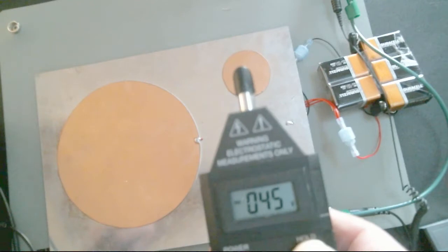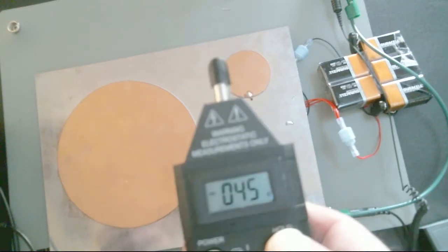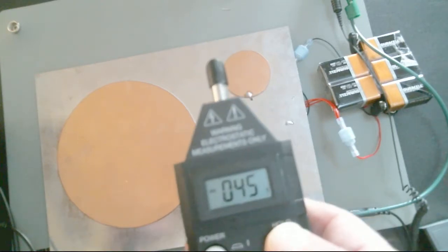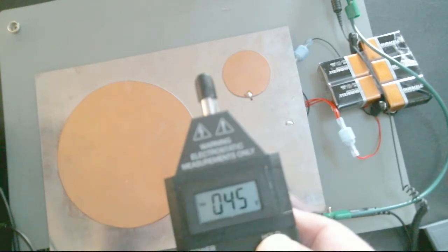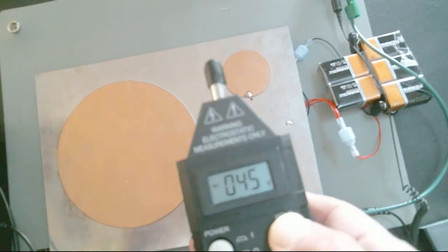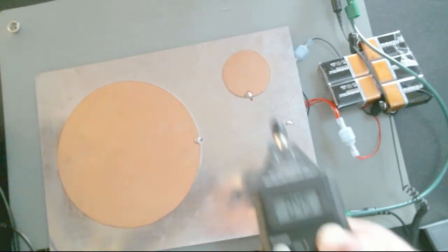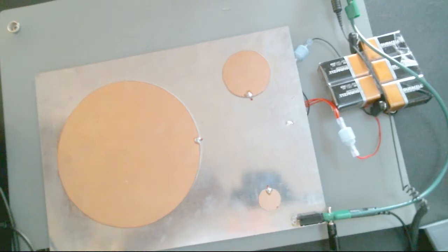Well, as a rule of thumb, the measurement area, the diameter of the measurement area, is four times the measurement distance. Therefore, with only a few millimeter spacing between the measurement and the measurement distance, the circular area of the measurement is in the millimeter range. So all three of these disks are small enough that the meter measurement is contained within the diameter of each of these three circles. Again, because of the small measurement distance, the small area of the measurement allows an accurate measurement on small objects.